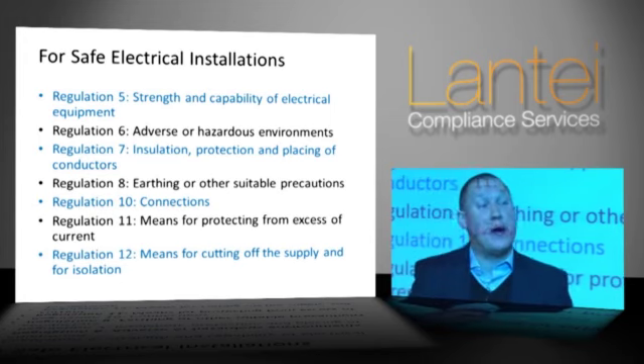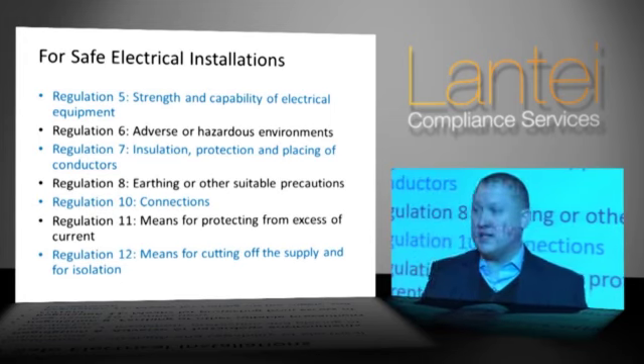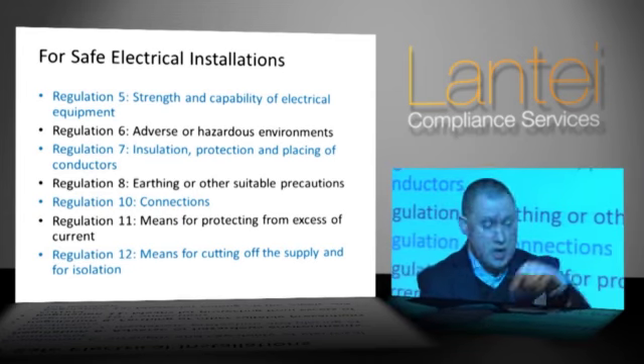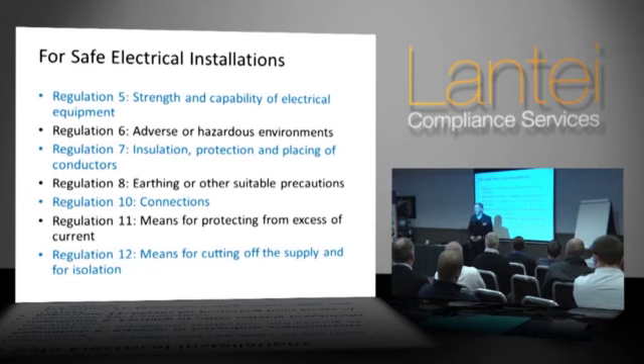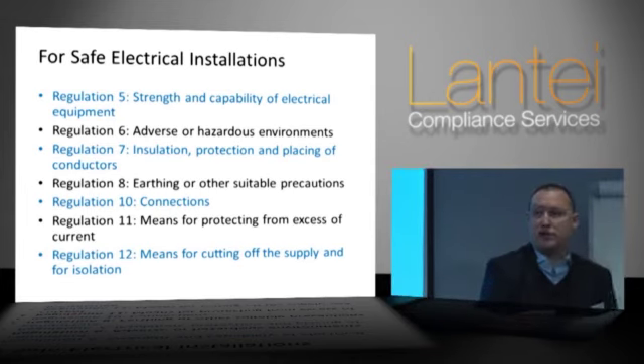Likewise, if we've got busbars, Reg 7 wants our busbars inside something like a busbar chamber or distribution board, some kind of enclosure again, so it stops us getting access to them and getting a belt from them. Another really obvious regulation is Regulation 8, which talks about a requirement for earthing systems to be in place, so we've got earth paths so that any fault currents in our electrical systems go down to the general mass of earth, they're neutralised, made safe in effect.